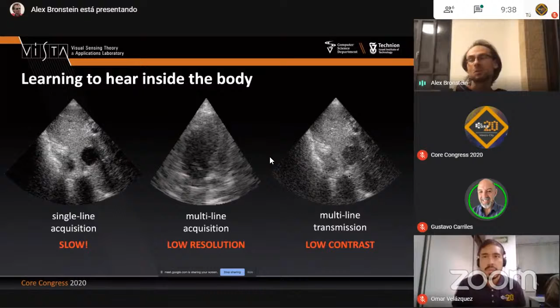And people actually developed methods for doing faster ultrasonic imaging. For example, multi-line acquisition. Multi-line acquisition defocuses the beam and then scans faster because you have a wider beam that you can move faster. Or another possibility is called multi-line transmission. In that case, you transmit a comb of pulses, and you sweep with that. And with that, of course, you can also decrease the acquisition time. The problem with these techniques is that multi-line acquisition has low resolution, and it creates a lot of artifacts because of this defocused beam. And multi-line transmission creates low contrast because of these crosstalks and basically a lot of clutter artifacts that are not present in the original image. And you need a lot of skill to be able to interpret this image.